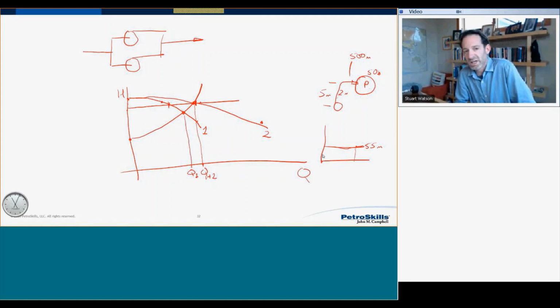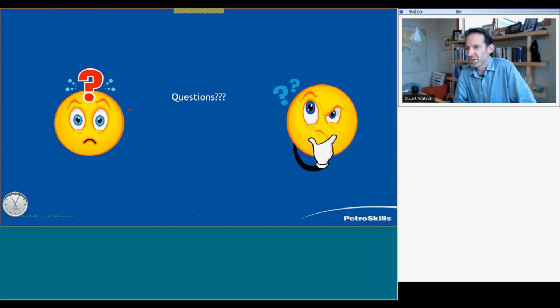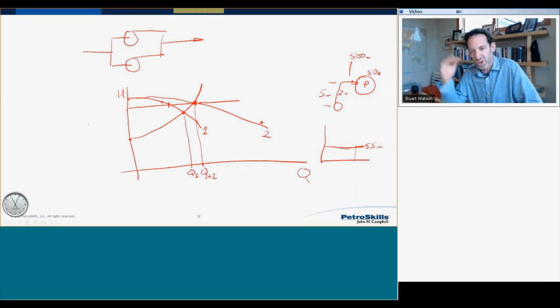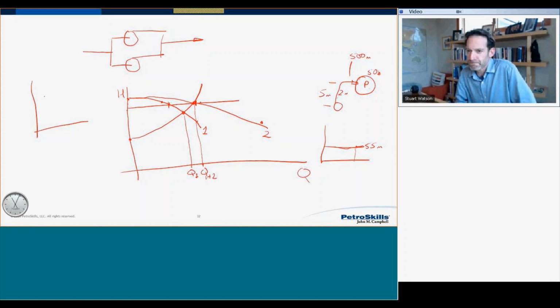And so you need to go through this process of, okay, take the two pump curves, add them together in terms of performance, plot them in Excel, put them on top of the system curve, and then work back to each individual pump. And then work out, is one pump going to back out the other pump? How close to the best efficiency points are we going to be operating each pump? And what's the effect on the NPSH of each pump and the power requirements of each pump? So I always go through that series of questions with that process. So hopefully we've answered some of your question there. Yeah, it's just about bringing your points in.